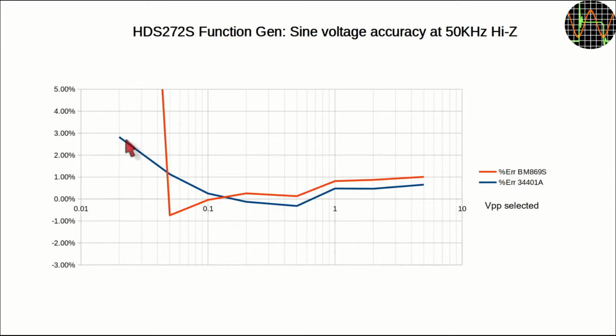The blue trace is the same test, but using the Agilent 34401A instead. This bench meter has similar caveats as the BM869S. For the 34401A, the AC signal must be at least 5% of the range, but in this case, the lowest range is 100 millivolt, so 5% is 5 millivolts, and therefore the 34401A can measure a 7 millivolt signal with some hope of valid results.